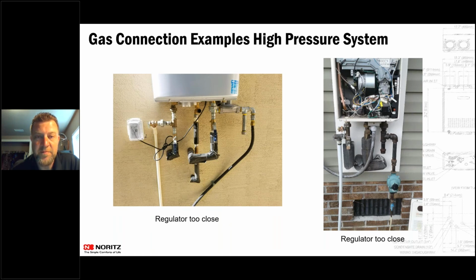I'm a plumber at heart. I've plumbed for many years and worked with a lot of gas lines, and it will help pull through, but it's not magic. It's not going to pull 199,000 BTUs through a half-inch line 100 feet. A lot of our units are half-inch capable. I call them half-inch capable, not half-inch ready. You still have to have enough gas in that line for it to work correctly, so you still need to size it. If it's close, it will help you fudge it a little bit, but it's not going to help you gain 100,000 BTUs.